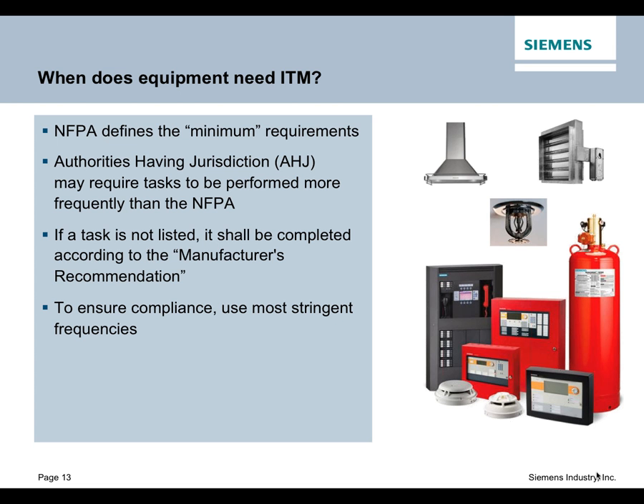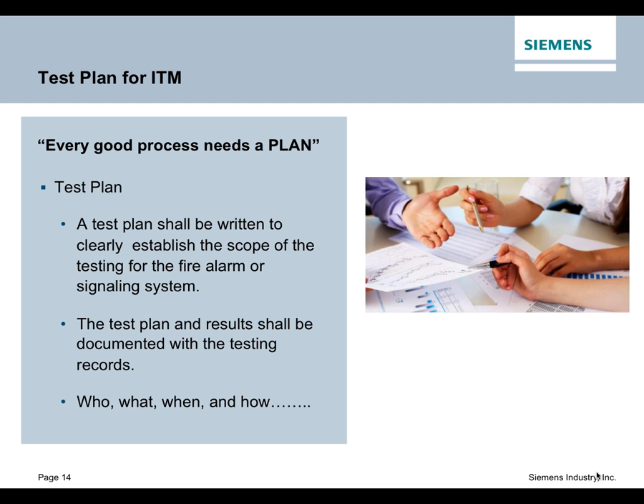This is very true if you have some specialized gas detection sometimes and specialized cutting-edge fire suppression systems. You may not find those listed in the NFPA code today, and you will be guided to follow the manufacturer's recommendations. But in any case, you always want to make sure that you use the most stringent of frequencies as you take a look at these different charts and graphs that we'll be looking at in a second.